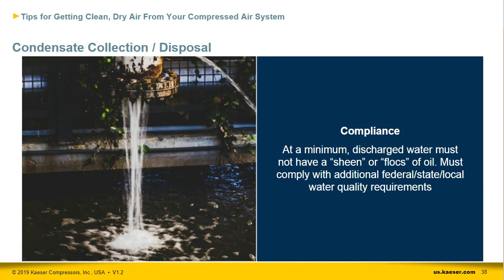So now we've removed the condensate from our compressed air system, but what do we do with it? Because condensate contains oil, we can't just put it directly into wastewater systems. Treatment's required to separate enough oil from the water to make the condensate safe and legal for disposal. At a minimum, discharged water can't have a sheen or flocks of oil, and you may have additional state and local requirements to be aware of and comply with.